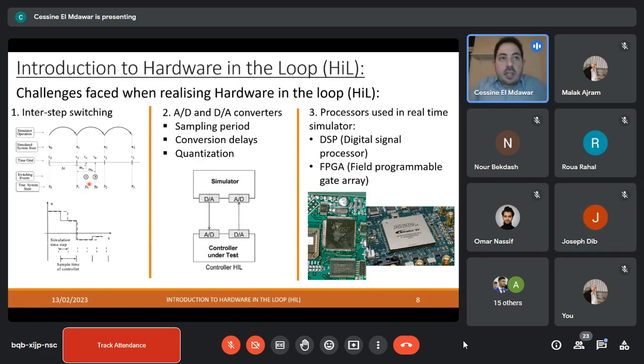So, as I was saying, assuming the controller sends point A and point B data to the real-time simulator, but the simulator is only able to compute at T1 and T2, it's going to skip point A completely because it only receives data at those points. To avoid losing data, we need a real-time simulator able to compute at a much faster rate, detecting all the points being sent, and this is a challenge in realizing hardware in the loop.